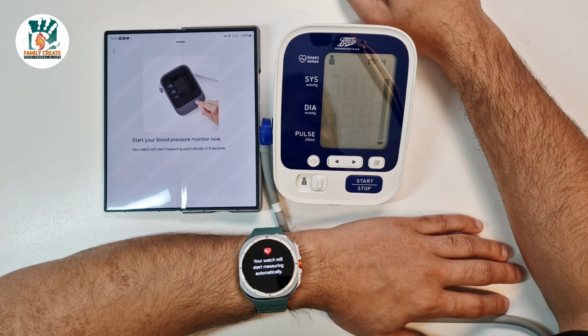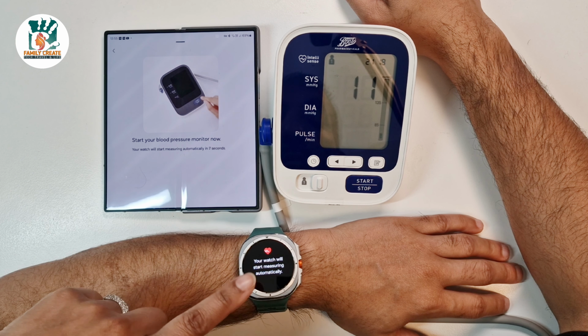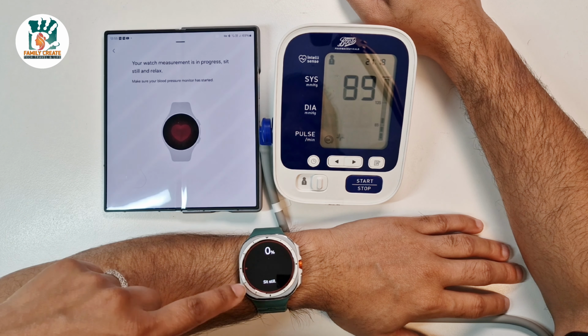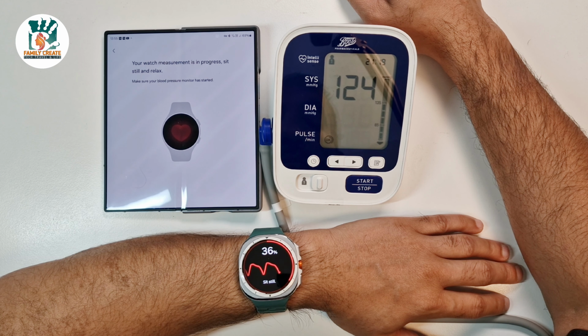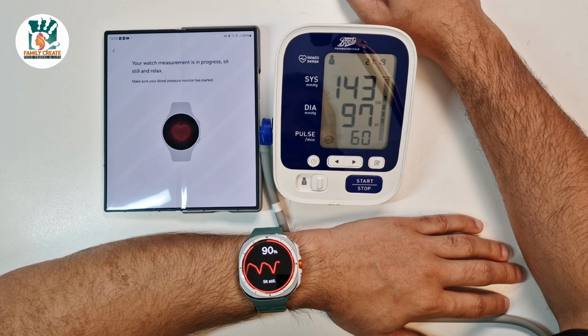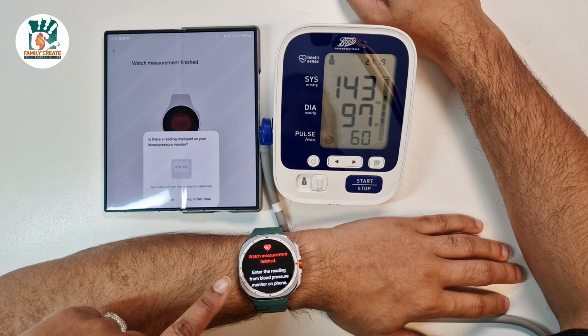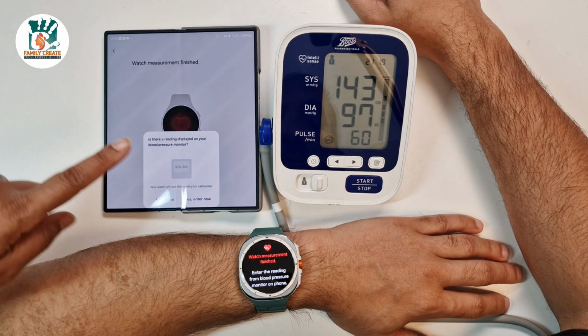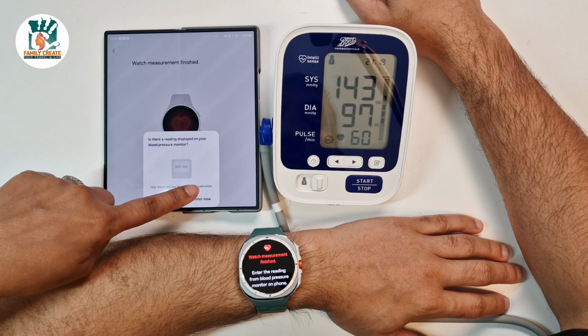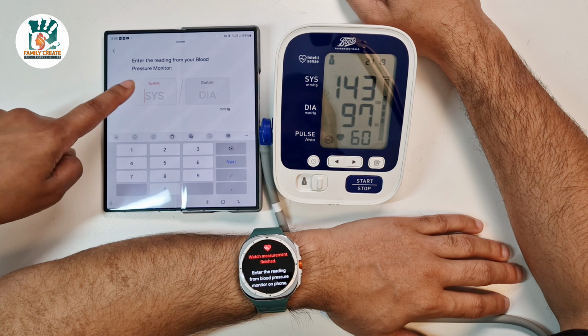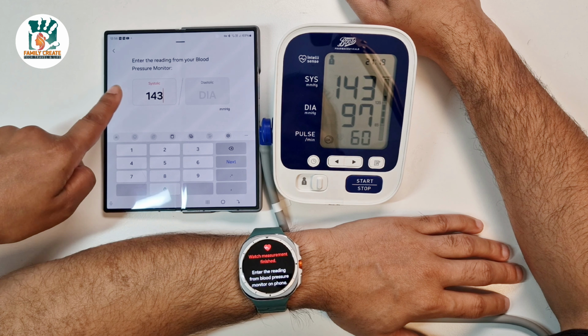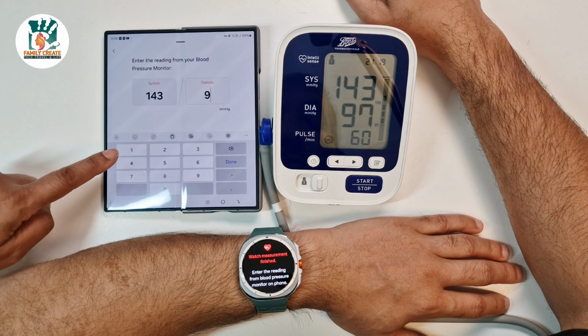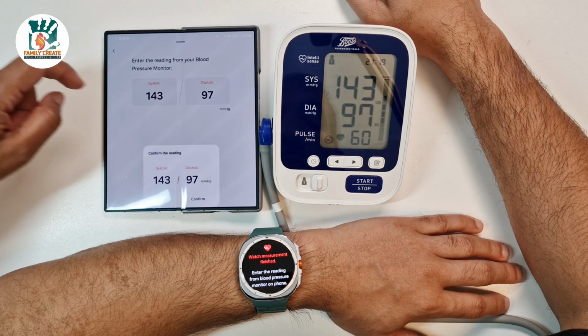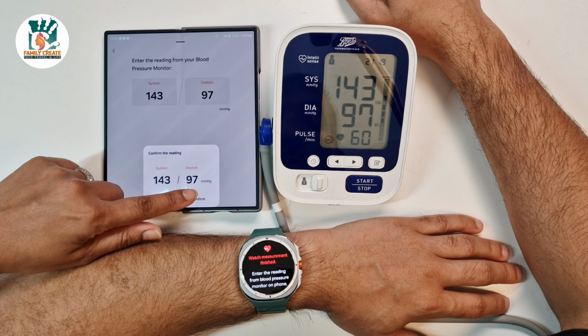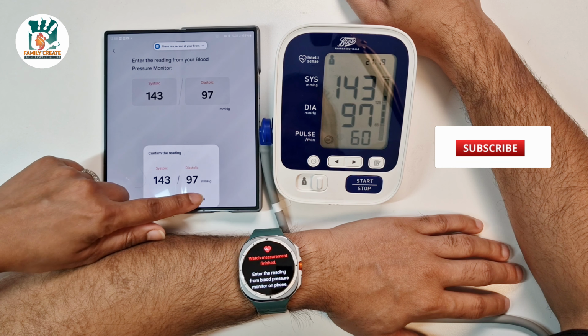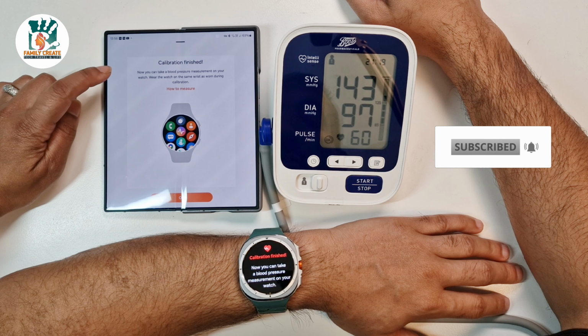Press start, and the watch is giving the instruction that your watch will start measuring automatically. Sit still. Same instruction on the phone as well. So, and the watch is still going. Okay, so the watch is now saying watch measurement finished, to enter the reading, and we've got the same instruction on the phone. So we're saying yes, enter. So we'll enter the reading, 143 over 97. Done. And it's asking to confirm the reading. Just say confirm. So it's saying calibration finished.